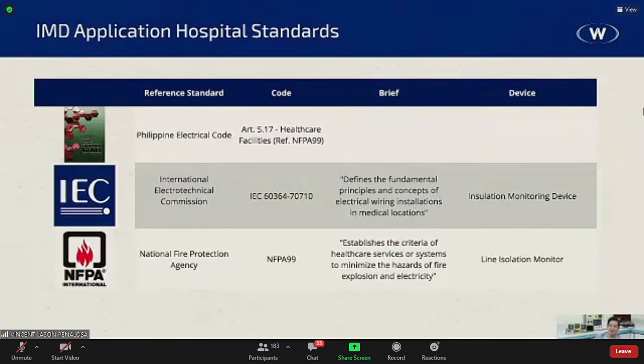Now, what are the standards? As I mentioned a while ago, you have the Philippine Electrical Code, that's Article 5.17, which we reference to NFPA 99. We have the IEC 60364-7-710. And then you have the NFPA 99. Now, basically, the IEC defines the fundamental principles and concepts of electrical wiring installations in medical locations. The NFPA basically establishes the criteria of healthcare services or systems to minimize the hazards of fire, explosions, and electricity. Now, they use two different things. The IEC uses the insulation monitoring device, and the NFPA basically uses the line isolation monitor, right? But both of them will have isolation transformers.